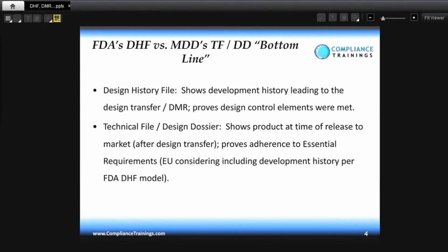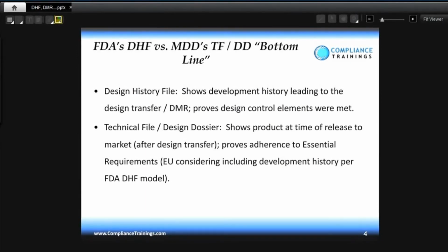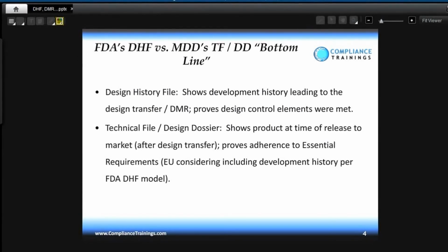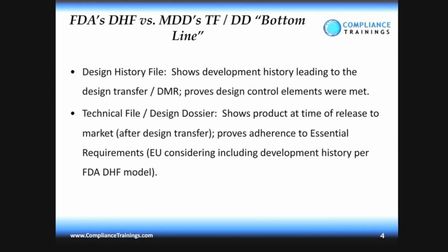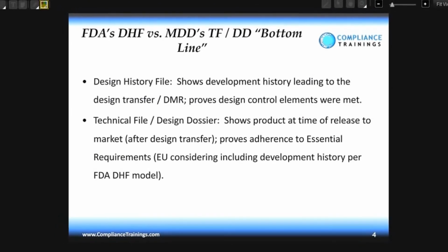As you change the product, you have to update your technical file design dossier and have it re-audited by your notified body. And the notified bodies do differ slightly in what they like to see and focus on, so you have to take what I present here with a grain of salt, recognizing that your notified body may have a slightly different format or different focus than other notified bodies. And again, my discussion here is based on my personal experience and that of my clients with specific notified bodies, which may not totally agree with what you may find when you deal with it.